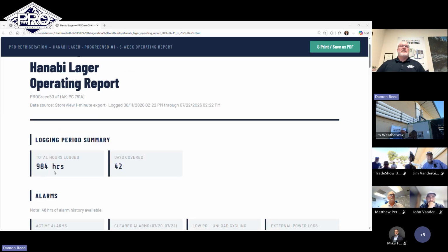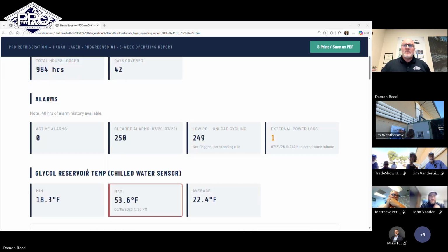So our logging period on this one is 984 hours captured, but these records and data sets being analyzed are by the minute. So it's a total of 42 days that we have covered of operating data. Because we did such a long draw in time, we only have a 48-hour window of the alarm history. One of the things we noticed right away: we have 0 active alarms and 250 cleared alarms, which I'm going to talk about.